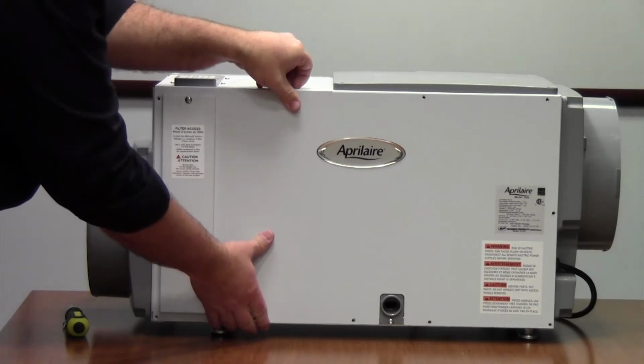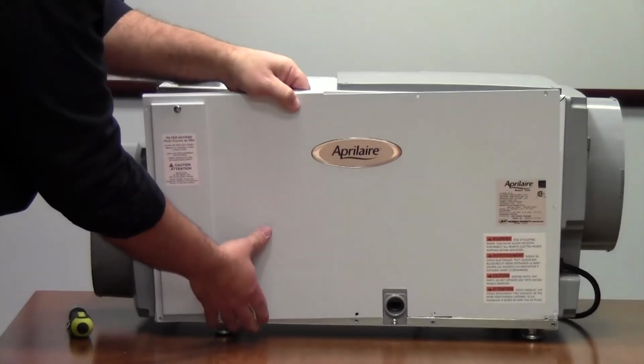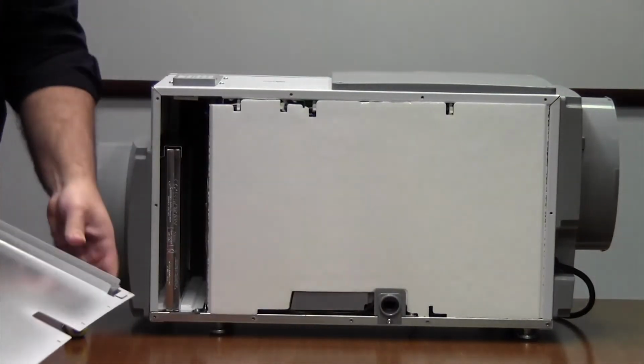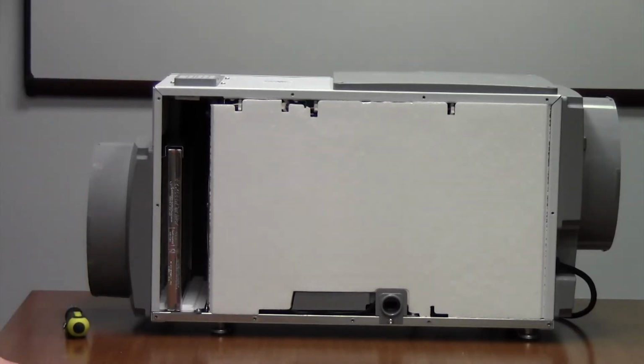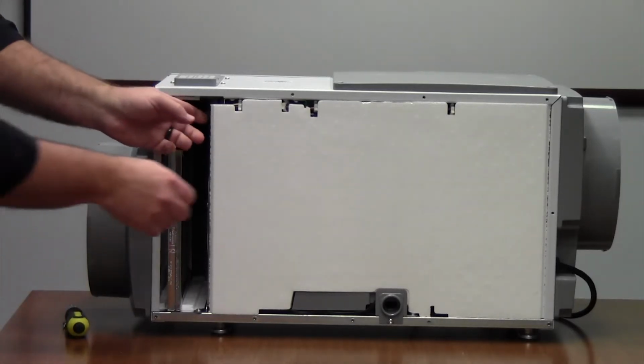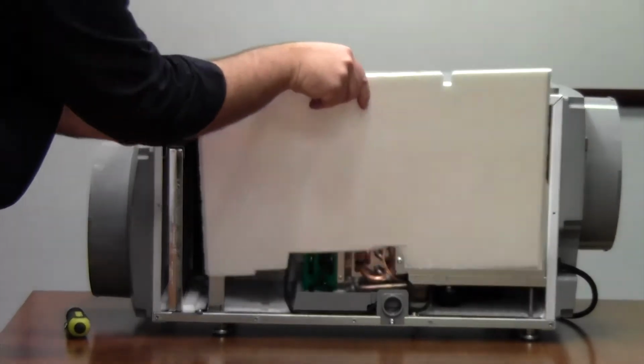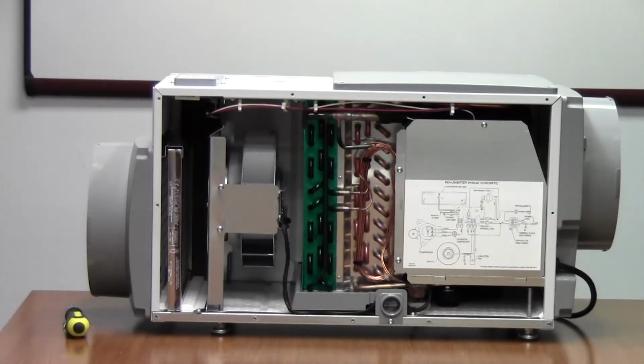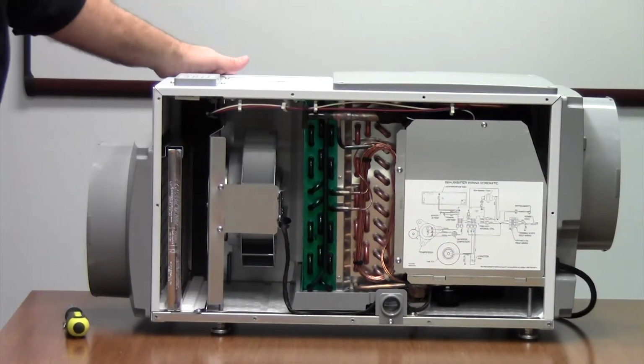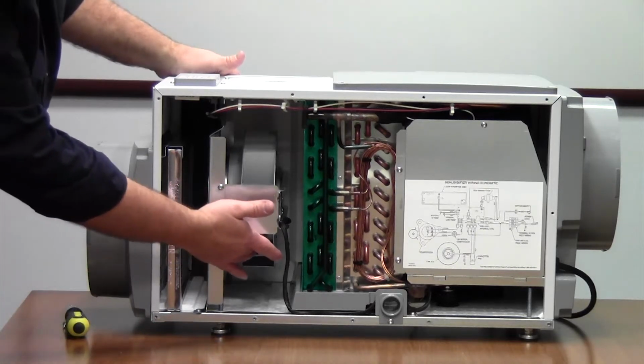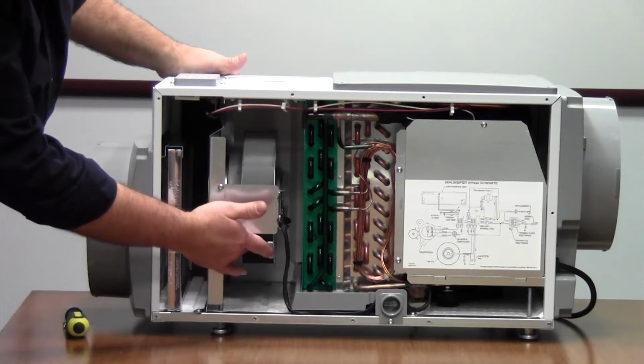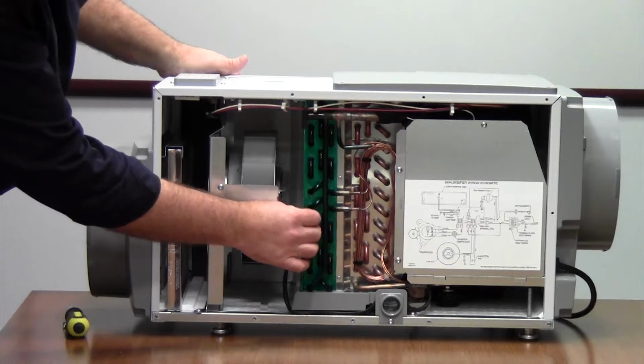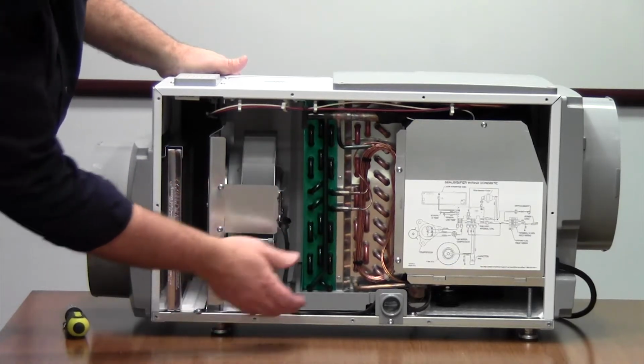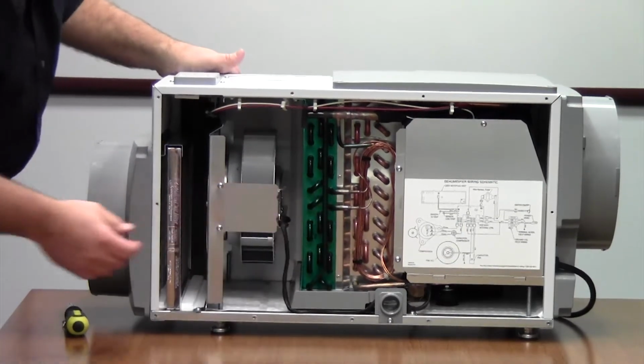Okay, that's the last screw, and then we'll remove this whole side panel. We can remove this piece of insulation. And now you can see the internal components. You can see our blower wheel in here. It's an impeller type wheel. The coil with the E-coating on it. This is a cap tube design.